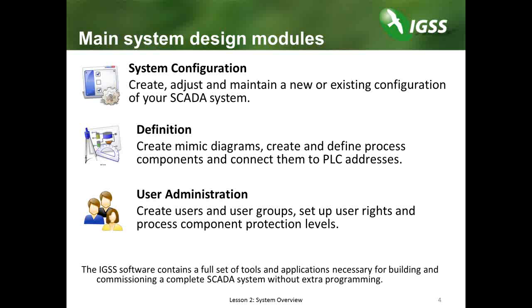These are the main system design modules — the modules that will be used by the system integrator or system designer who typically will be creating and setting up the project for the customer. The system configuration module is where the system designer creates, adjusts, and maintains new or existing configurations, giving you the basic working parts of your SCADA system and laying the foundation for the rest of the project. The definition module is used to create the mimic diagrams as well as all the required process components and connecting these to PLC addresses in the process. The user administration module is used to create users and user groups, as well as setting up user rights and protection levels for individual process components. Generally speaking, the IGSS software contains a full set of tools and applications necessary for building and commissioning a complete SCADA system without extra programming.